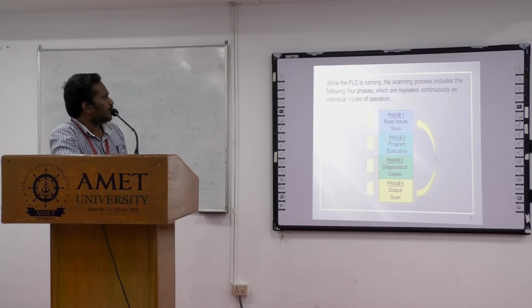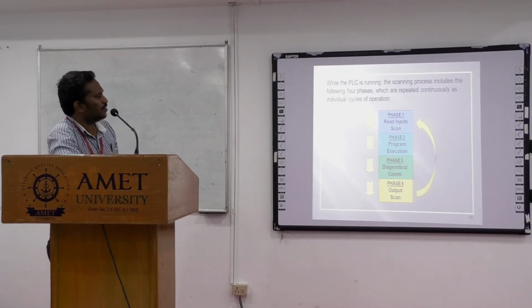While the PLC is running, the scanning process includes the following 4 phases, which are repeated continuously as individual cycles of operations. Phase 1: the PLC will scan the input module, that is called the read input scan. All the inputs connected to the input module will be scanned by the PLC in phase 1. Phase 2, program execution: the PLC will scan the program in phase 2. Phase 3, diagnostics and communication.